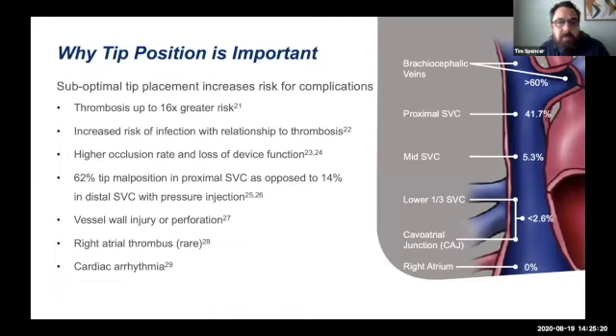There's a 62% malposition rate when the catheter tip is sitting in the proximal SVC, as opposed to 14% or lower when the catheter tip is sitting in the distal SVC and the catheter is power injected. So certainly there is a much higher degree of risk that if the catheter tip is too high and it's being used for power injection, the catheter will malposition due to the power injection process.